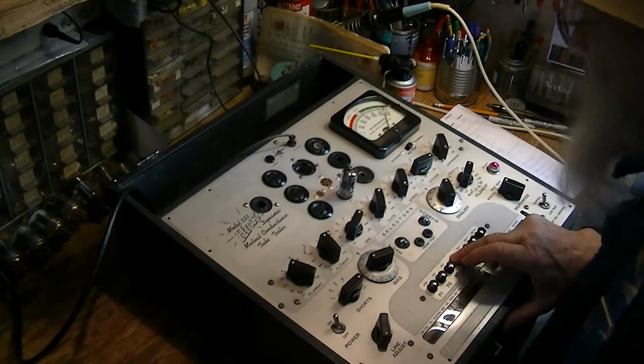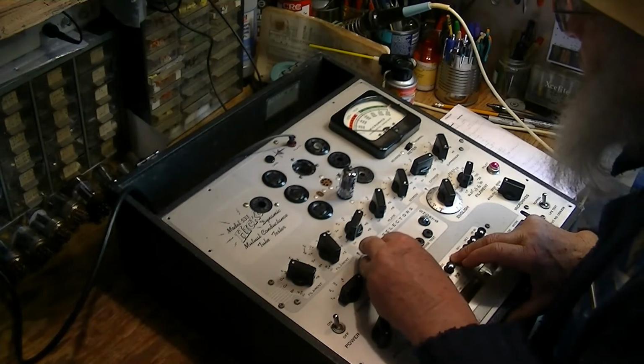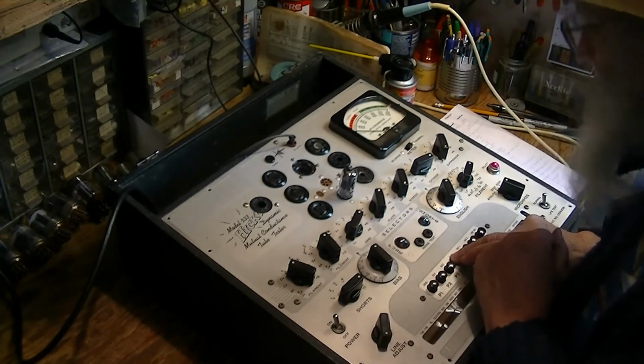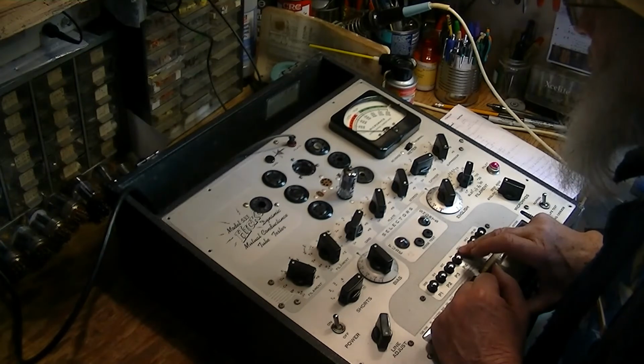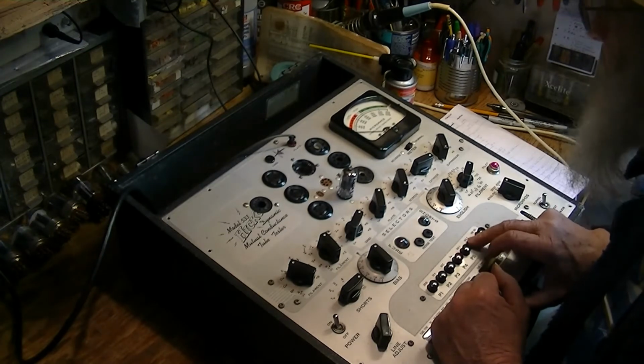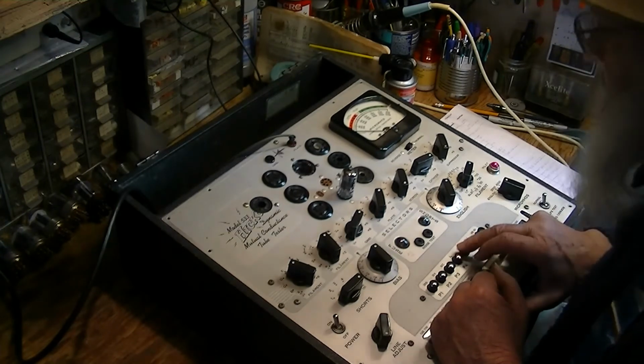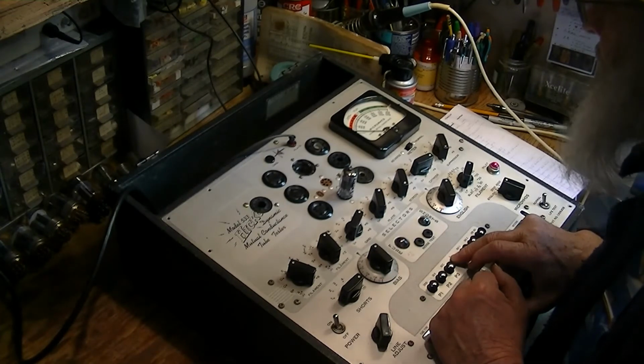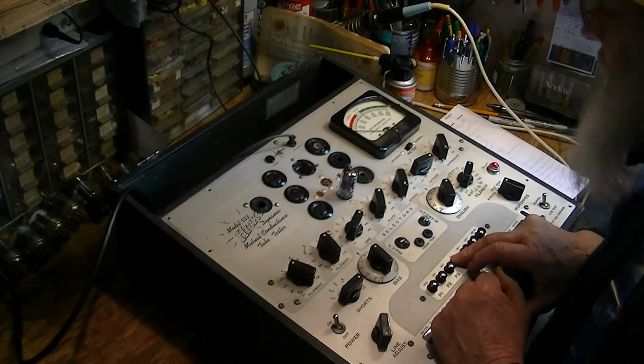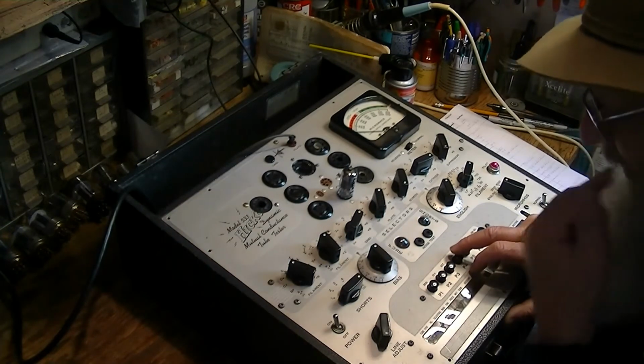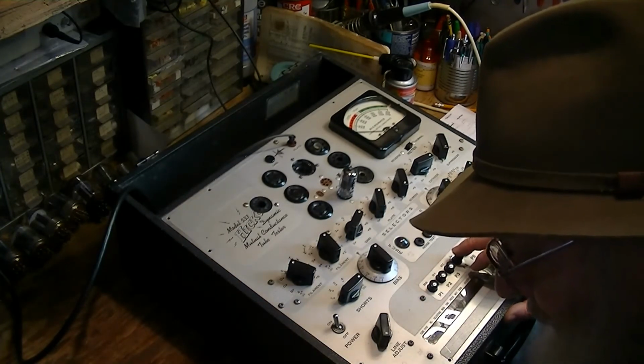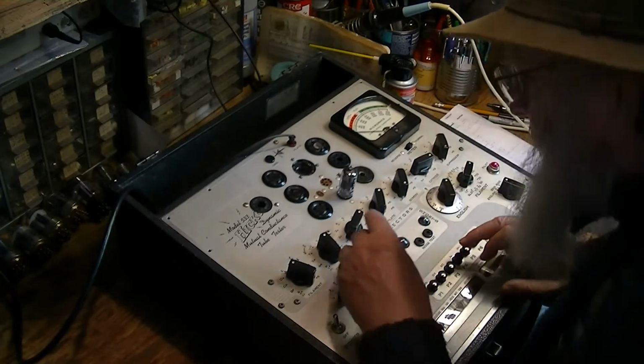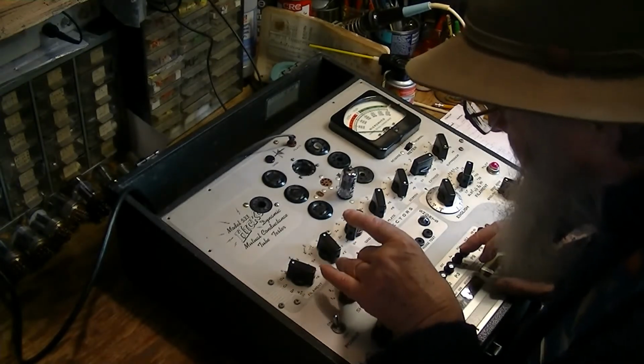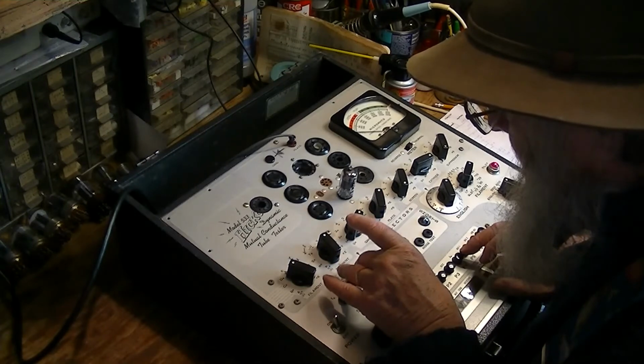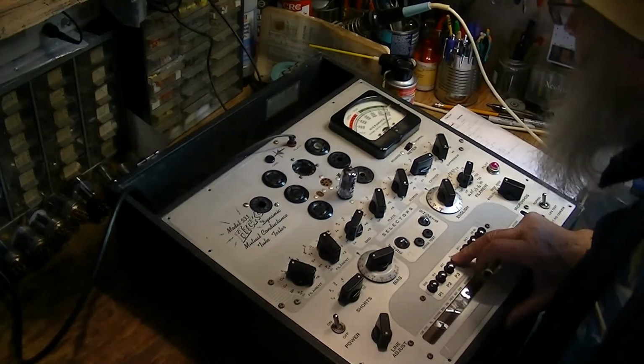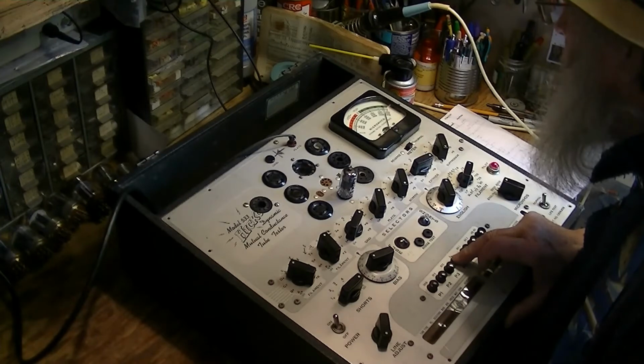So here we are. We're going to crank the bias down until it reads 100. Then we're going to do the gas test. And it shouldn't really go up any more than what you set it at. It might go up 50, but it shouldn't go up much. And this is sitting right on the money, right where it should be. So now let's go back to the proper bias setting of 24. And there we are, 2650.